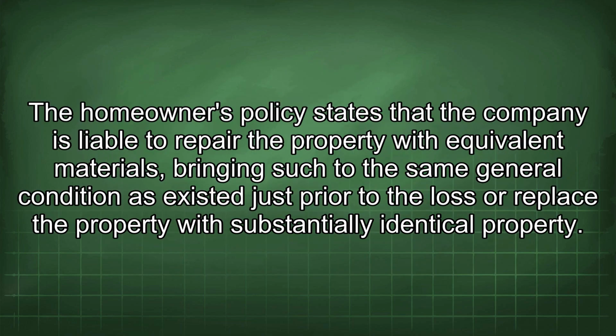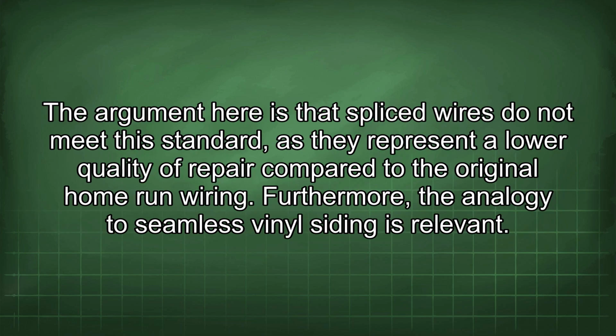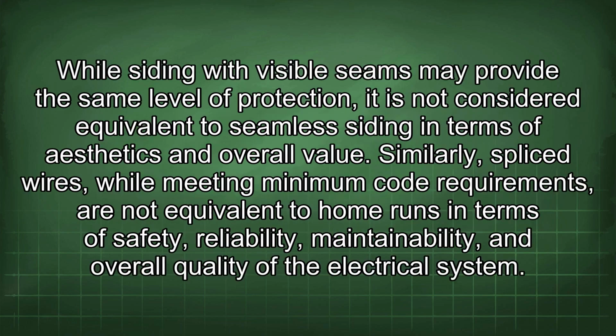The homeowner's policy states that the company is liable to repair the property with the equivalent materials, bringing such to the same general condition as existed just prior to the loss, or replace the property with substantially identical property. The argument here is that spliced wires do not meet this standard, as they represent a lower quality of repair compared to the original home run wiring. Furthermore, the analogy to seamless vinyl siding is relevant. While siding with visible seams may provide the same level of protection, it is not considered equivalent to seamless siding in terms of aesthetics and overall value. Similarly, spliced wires, while meeting minimum code requirements, are not equivalent to home runs in terms of safety, reliability, maintainability, and overall quality of the electrical system.